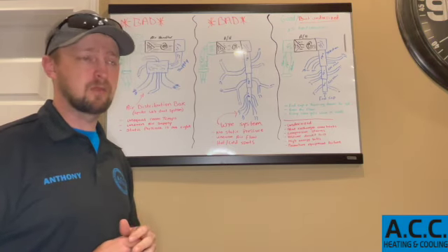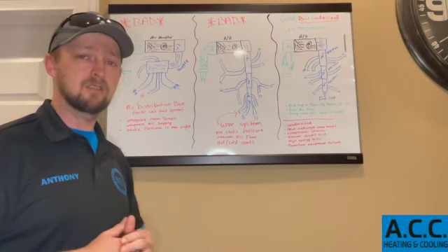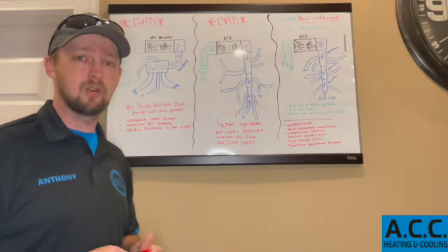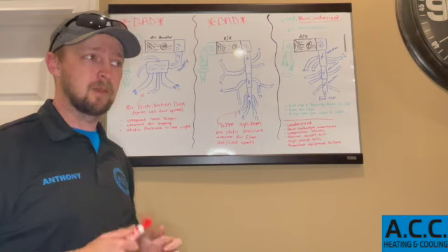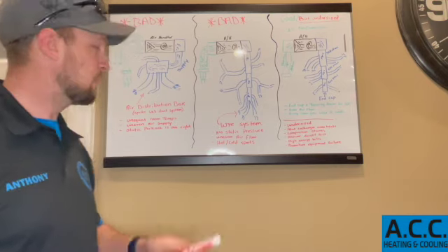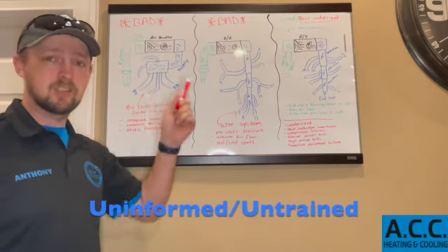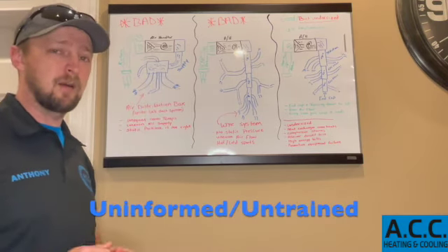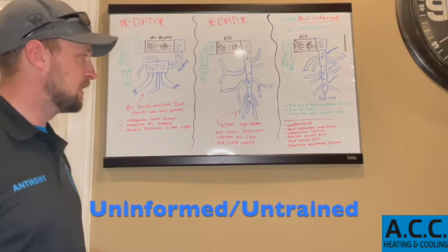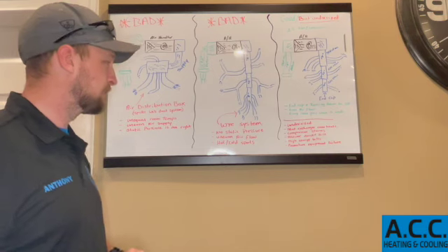Last year we probably did 8 or 9 jobs that were on 2-year-old or less houses that were just built. And what these new construction guys go and do is they throw in a duct system just to get the air out to the rooms. There's no rhyme or reason to it. There's no static pressure, which is a big thing that I'm going to talk about here in a second.